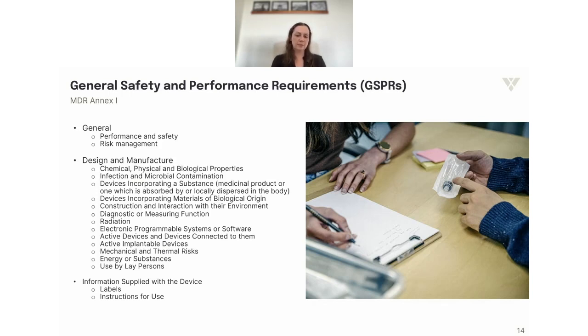The final section is probably what looks the easiest, but it's quite lengthy, and it's a lot of detailed requirements on the information that you supply with the device. So labels and your instructions for use and what those need to contain. Now, when you do the general safety and performance requirements, I strongly recommend that you really early in your process identify which ones apply, because you do have to address the ones that do not apply with adequate justification. And for those that do apply, you need to have those methods such as standards, guidances, common specifications, etc. So you really need to build these into your design control process as early as you possibly can. Something else to note is that there are lots of elements of risk, particularly in this design and manufacture section, that you need to consider in your risk management from the beginning.